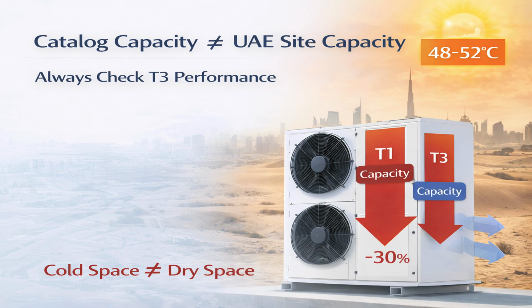So when a unit is selected based only on T1 data, it may appear perfectly adequate on paper. But once installed at site, its real capacity drops exactly when the cooling demand is at its highest. This is why selecting equipment based on T3 performance, not just T1 ratings, is so important.